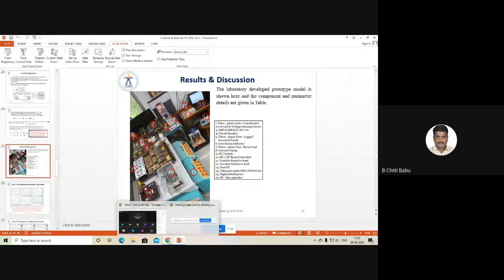Actually, the voltage available at PCC is basically the voltage of the grid. So that voltage is basically the voltage at PCC. Actually, PCC is not a real connection where you are going to connect. The PCC is not even well defined by IEEE. As per the IEEE definition also, PCC means the point at which the non-linear loads are connected in the power system. So it doesn't have a correct definition for PCC.